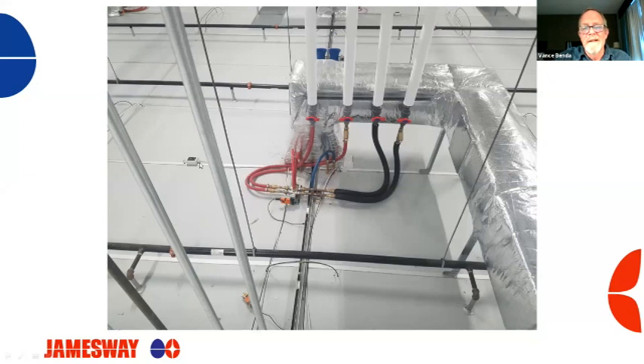and that puts it right in the center of your egg mass. And then you can see the wire goes in right here and goes into the low voltage side of your incubator. Low voltage is always on the left. This track over here is for high voltage. This does not mean that this wire is connected to your incubator. It simply goes into the low voltage track, up to the front, and up and out through one of these conduits over to your control panel. Very important to understand that the high temp backup alarm is not connected to your incubator in any way.